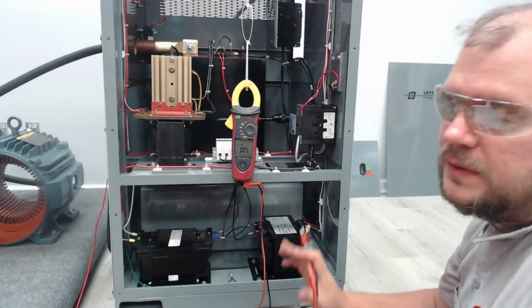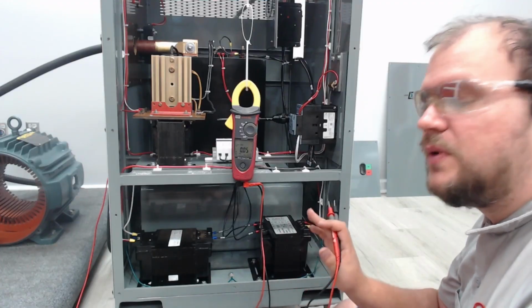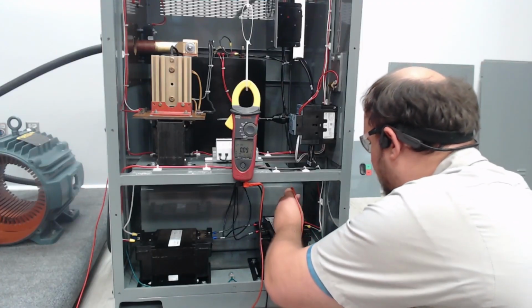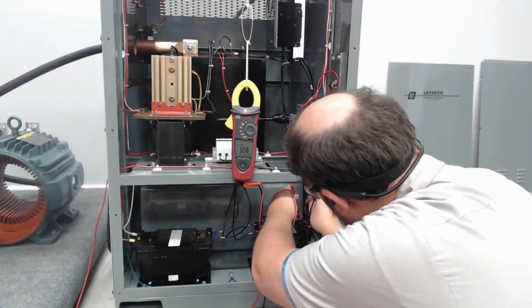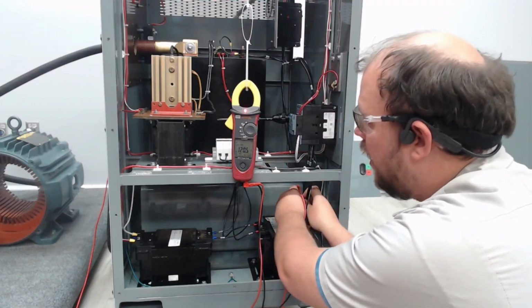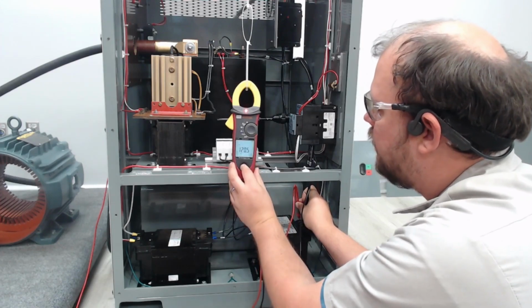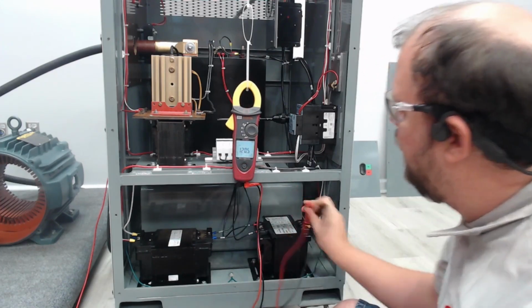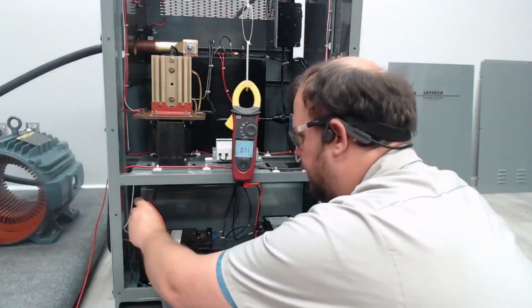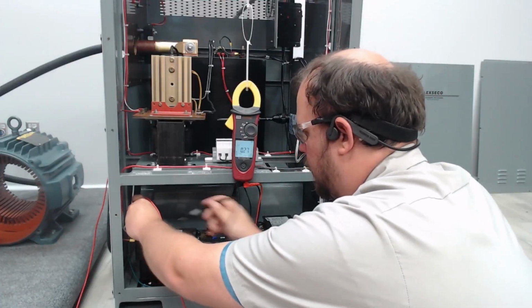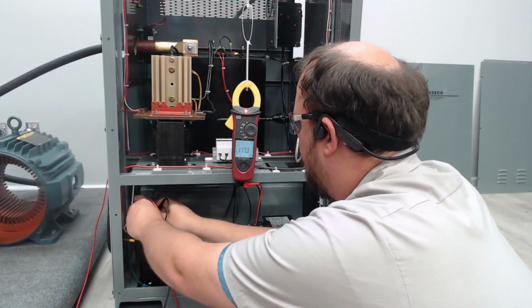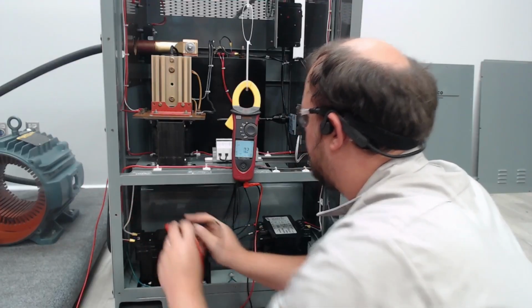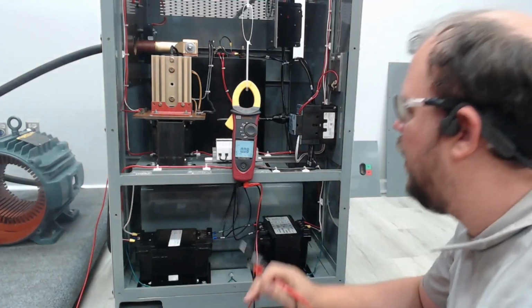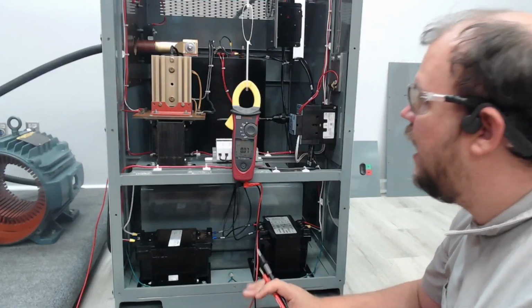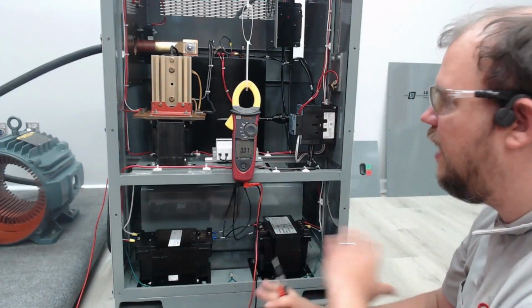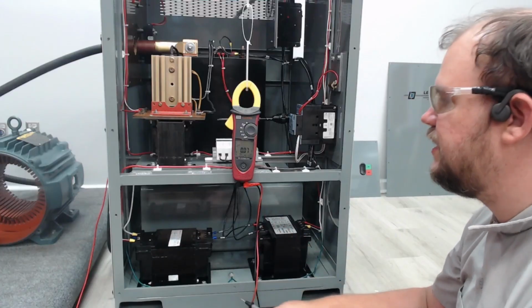The output, doesn't matter what's going in, output needs to be 120. It is AC, so you don't need to change anything on your meter. So that is 120. That is 120. Going over to this side. This one is 120. So that one is doing really well. It's reading good. Now this is a new unit. We took the panel off. It's easy access. It's very safe to do these readings.